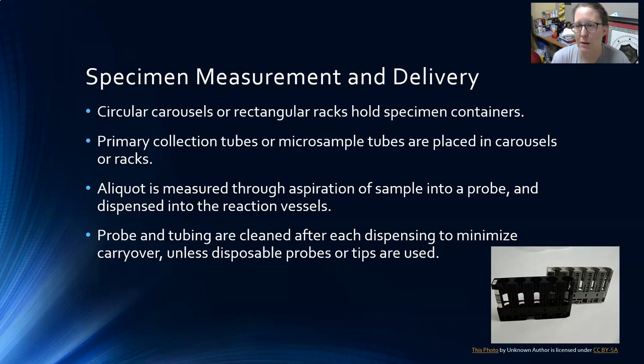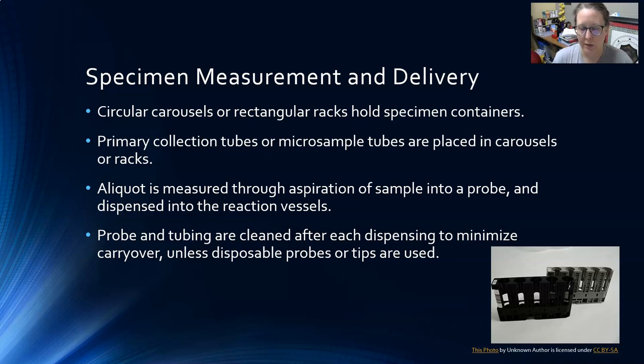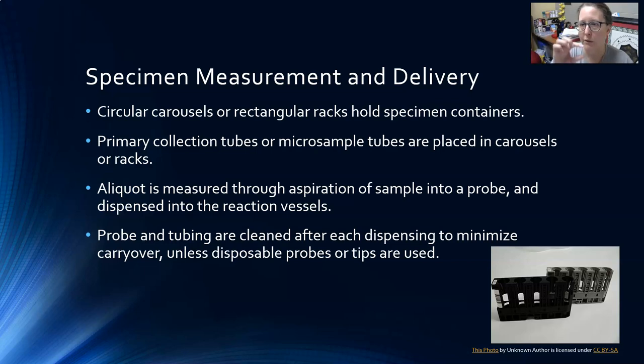They could also have adapters for small specimen cups, which would be for pediatric samples or low-volume samples from geriatric patients. Once loaded on the rack and fed into the analyzer, an aliquot is measured through the aspiration of the sample into a probe, and then it's dispensed into the reaction vessels — bits of it dispensed across different reaction vessels. An aliquot is a determined volume, a part of the sample pulled off.